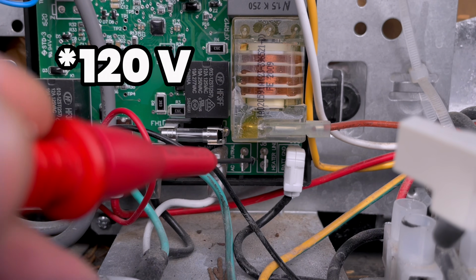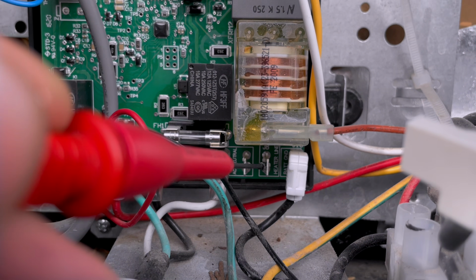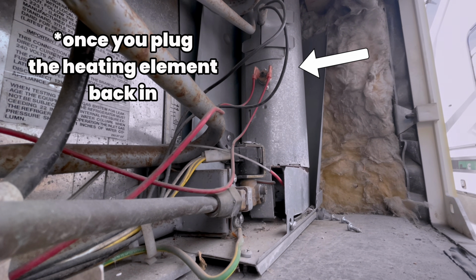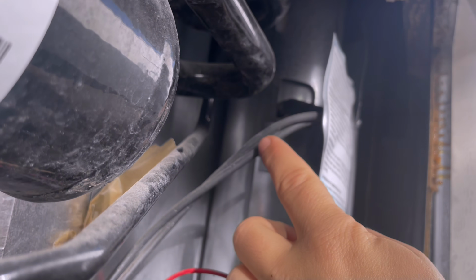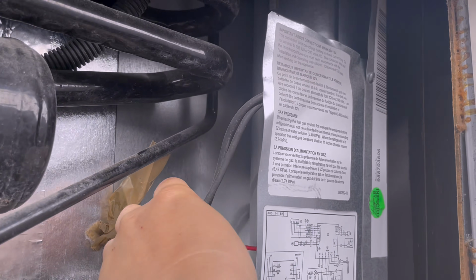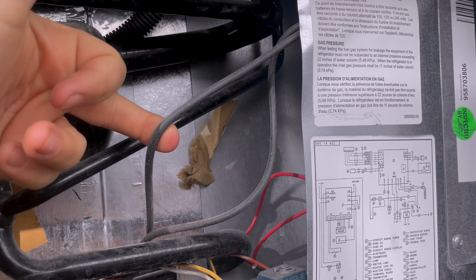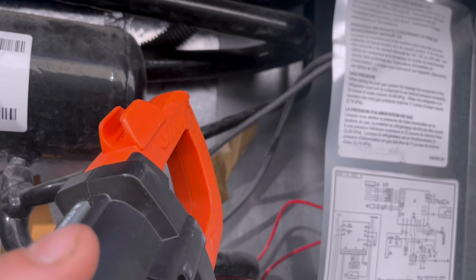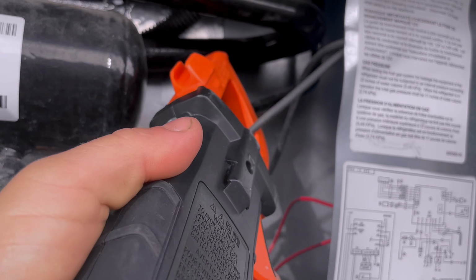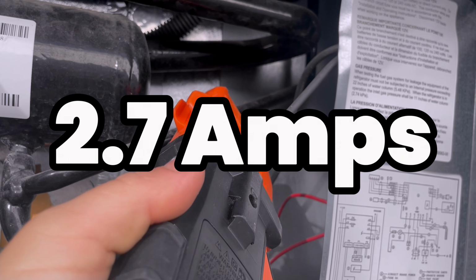If you have 120 volts on that pin, then this tube should be getting hot. If it's not getting hot, and you have a fancier meter that has an amp clamp, you can set it to AC amps, clamp around one of the wires heading to this heating element, and you should be seeing a reading in the realm of this number. I can't remember it off the top of my head.